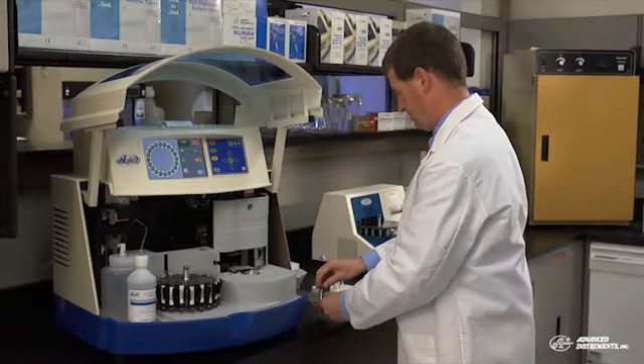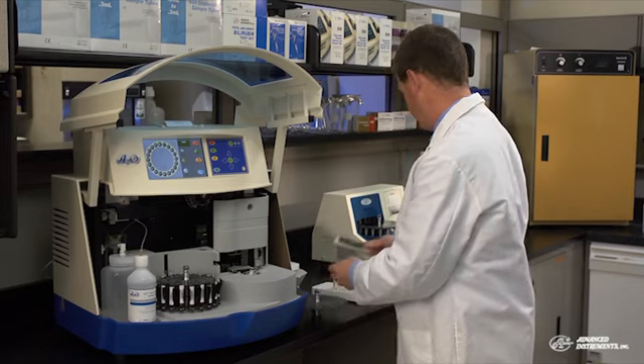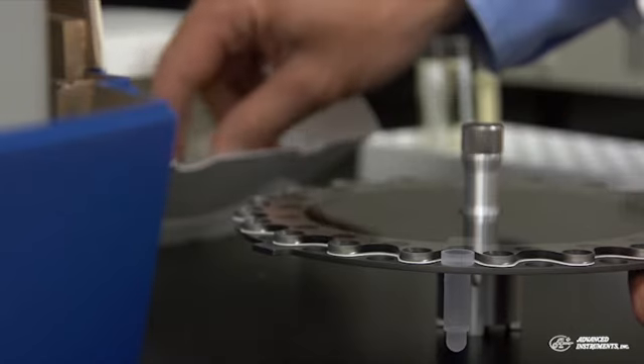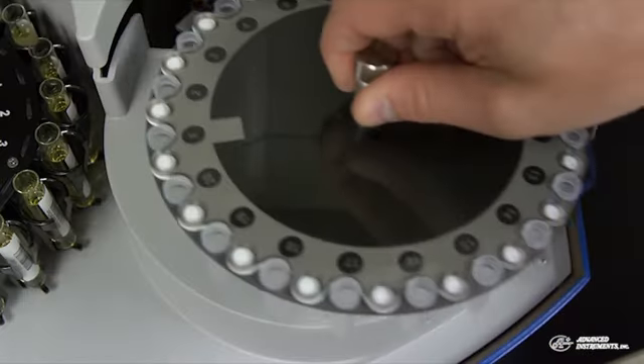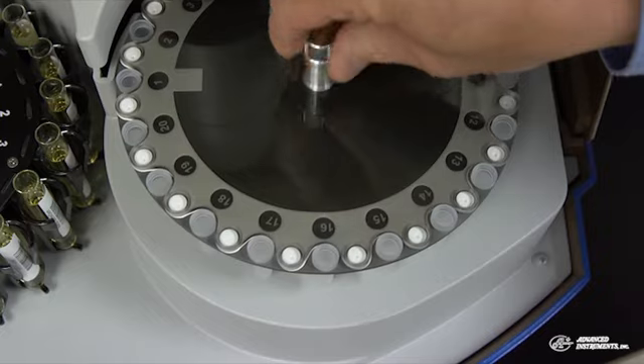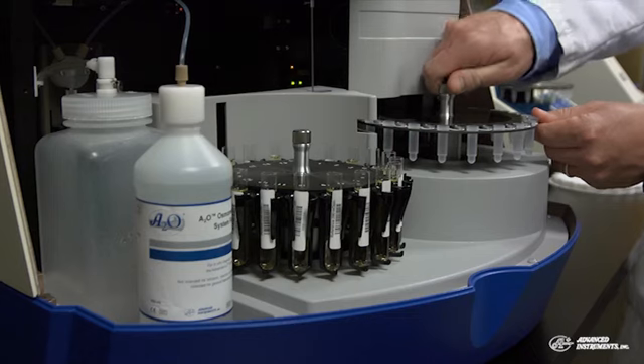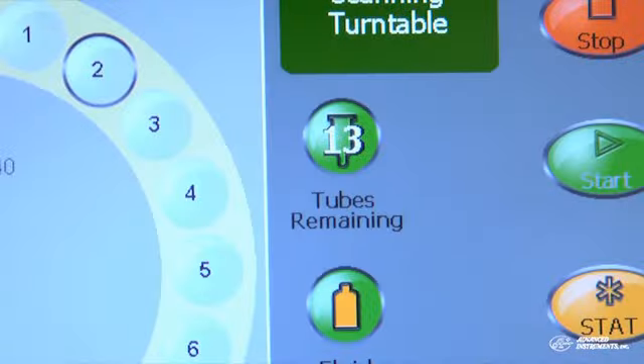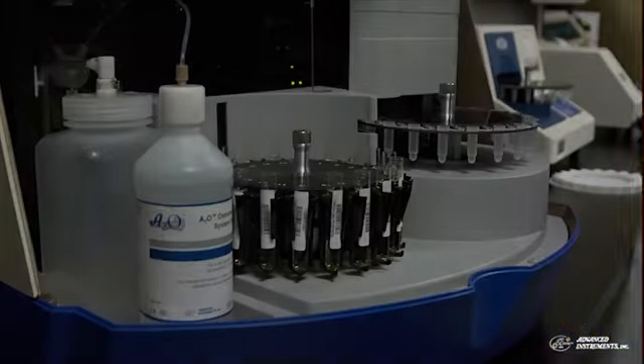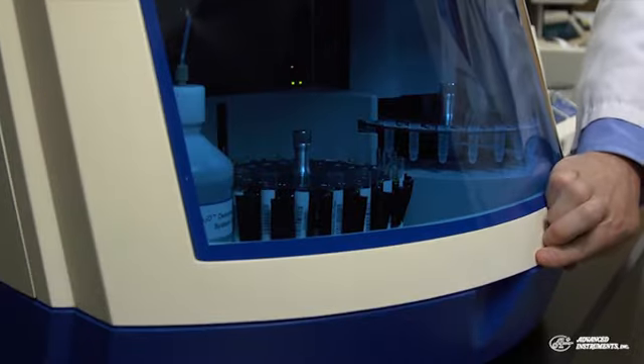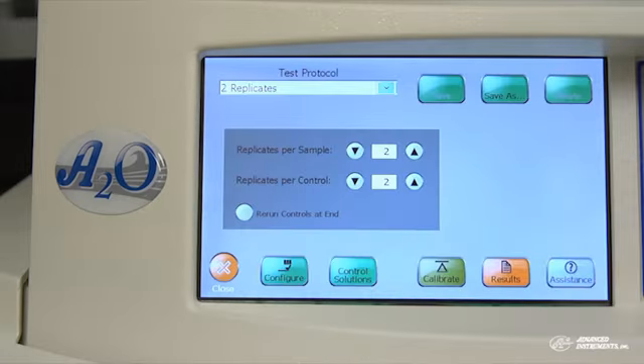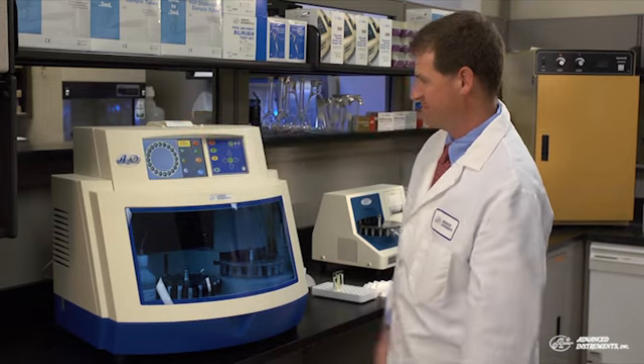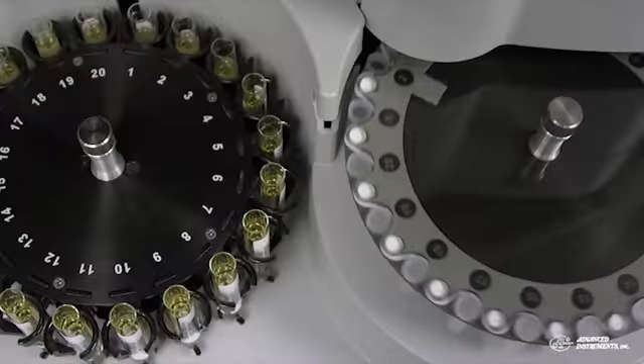Next, remove the osmometer carousel from the A2O and remove the sample cover. You can load up to 20 sample cups and a new wiper ring onto the carousel. Replace the sample cover and install the carousel back into the system. The A2O will automatically keep track of sample cups remaining and will prompt the operator when replacement is necessary. Close the access door and select the test protocol you wish to run. Press the Start button to initiate the test sequence. It's as easy as that. The A2O will take care of the rest.